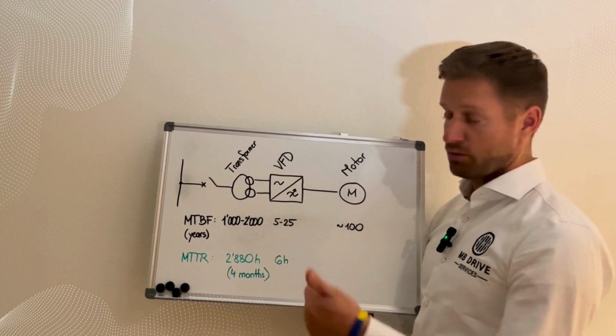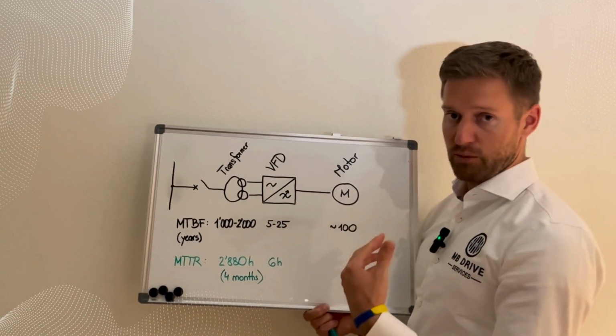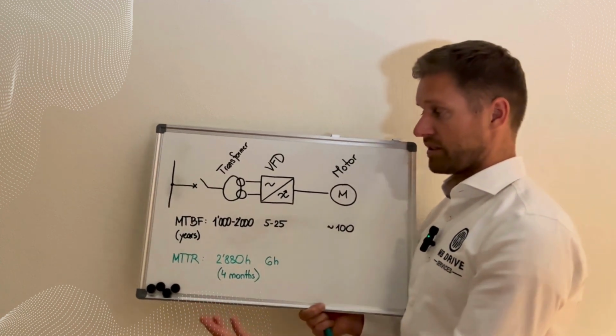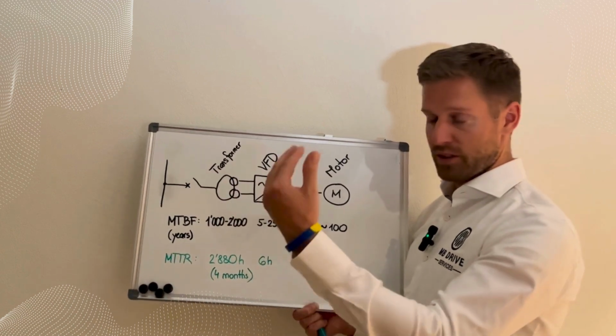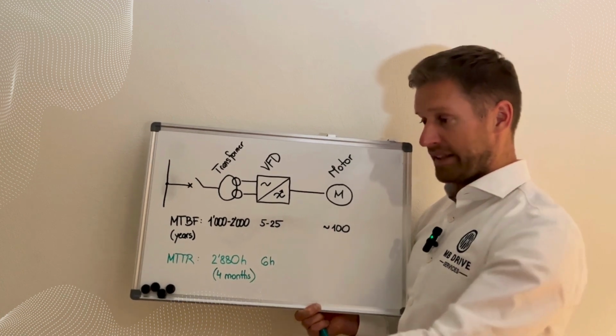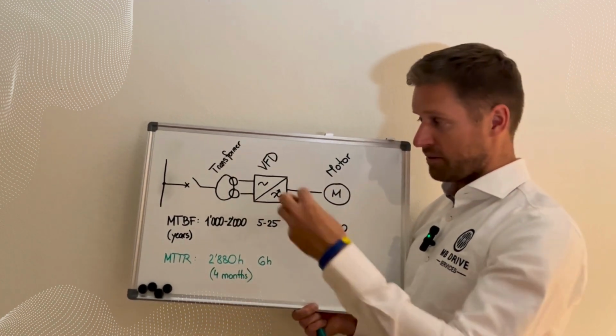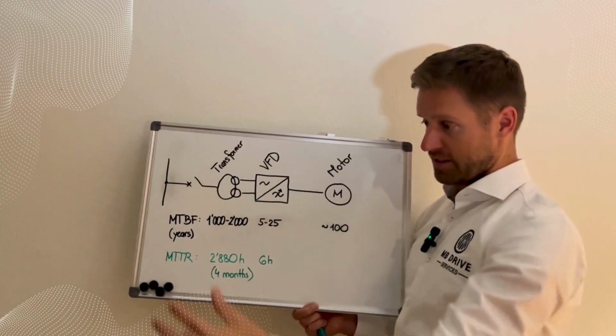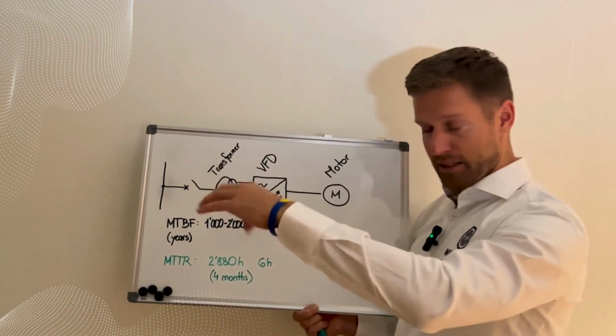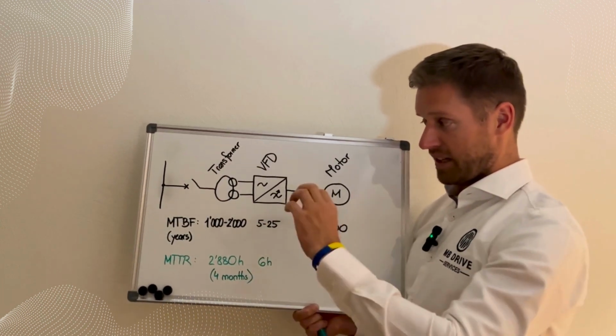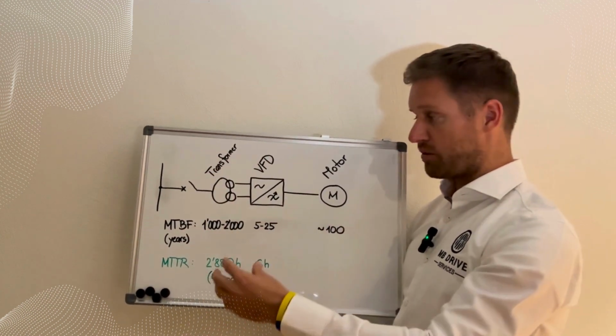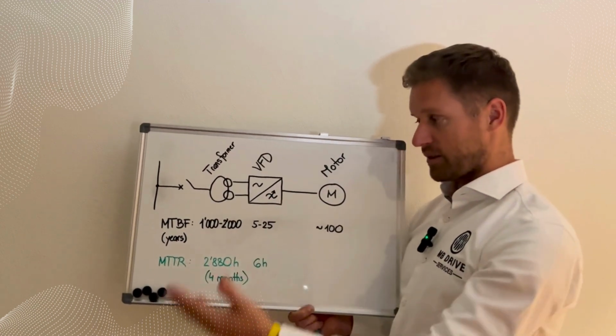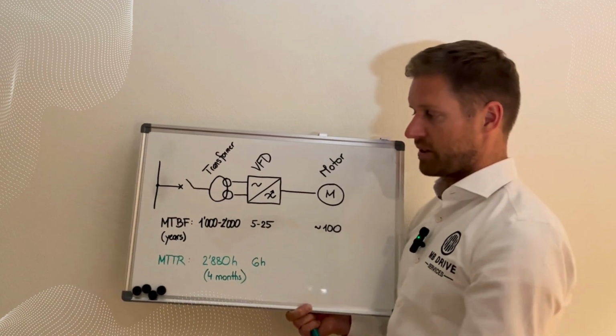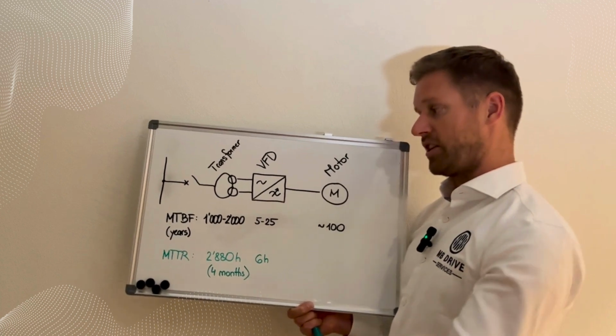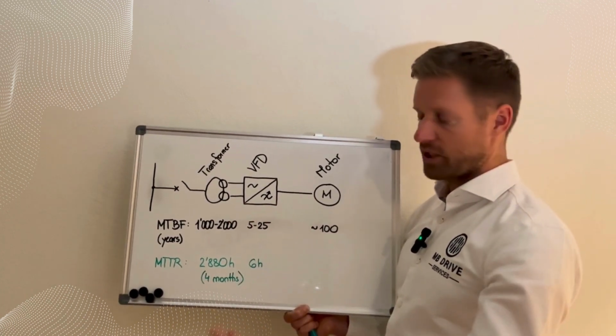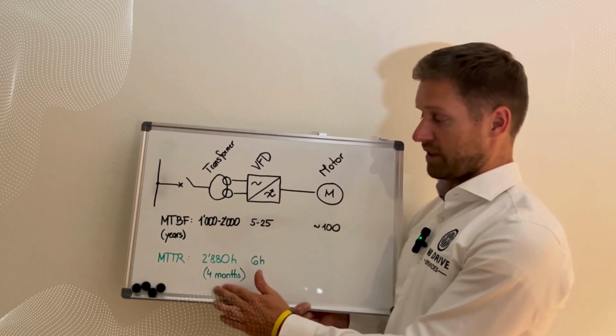So first you need time to manufacture the winding, and you need to ship the transformer back to the factory or to a service shop. If it's an oil transformer, you need to untank it, so remove all the oil, take the active part from the tank, disassemble, remove all the clamping, so disassemble the magnetic circuit, take the failed coil out, put the new one in, put everything back inside, test the transformer again, so repeat all the routine tests and factory acceptance tests, ship it back to site, install it, recommission. So this can take a very, very long period of time.